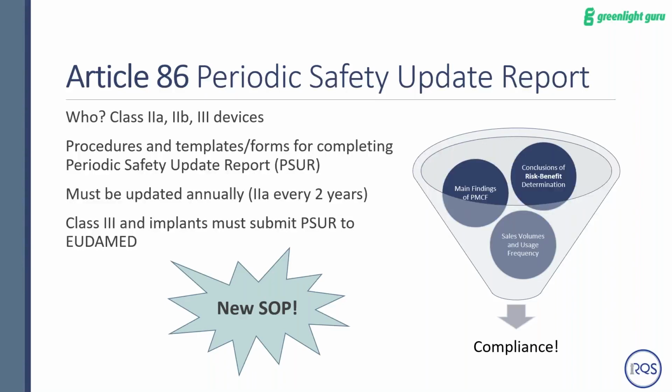Another thing is for Class 3 and implants. So you have to submit this safety report to the EUDAMED database. So we'll talk about that a little bit more as well. EUDAMED is this giant database that has all this information. I assume it's going to be similar to the FDA database that has 510(k)s and the MAUDE database and all those things. I think they're trying to create something similar on the European side for all the devices covered with CE Mark.